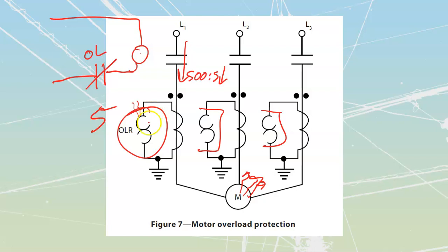Do note as well that this is the heater. This contact never opens. We've talked about the fact before that the CT should never be opened. My CT circuit in here will never be open because this overload itself, this is not the actual relay, this is the overload heater that's inside here. The overload heater is nothing more than a resistor. It does not have any switching elements. It's a resistor that gets hotter with more current through it, which eventually causes the actual overload element to trip out.